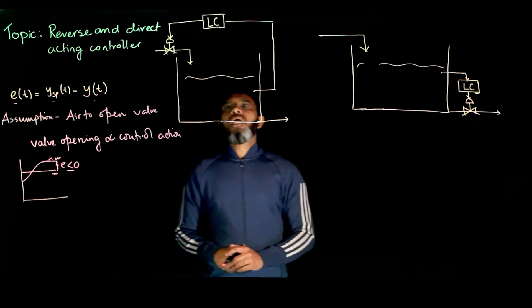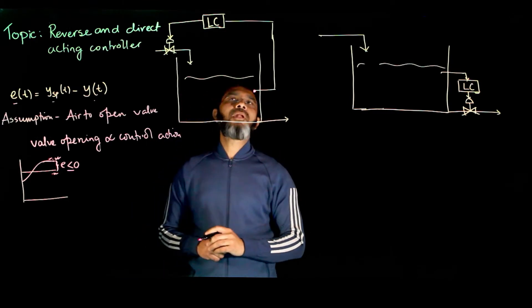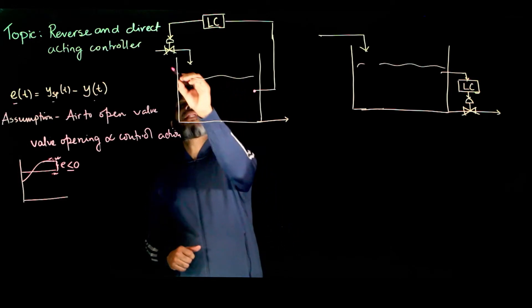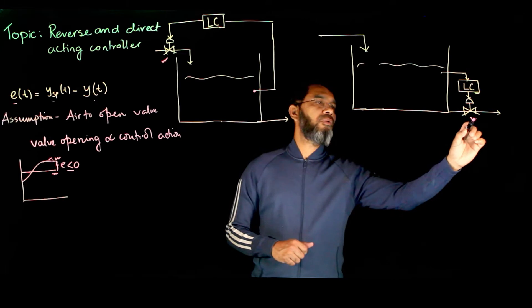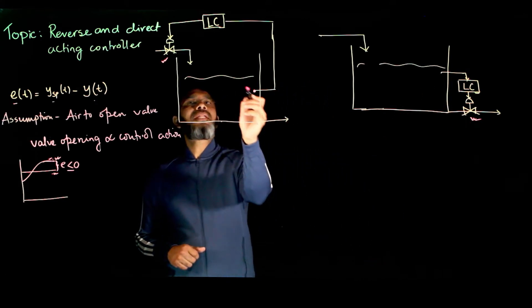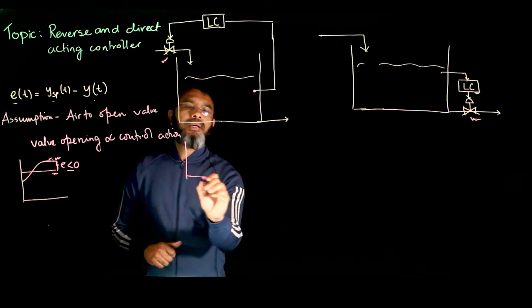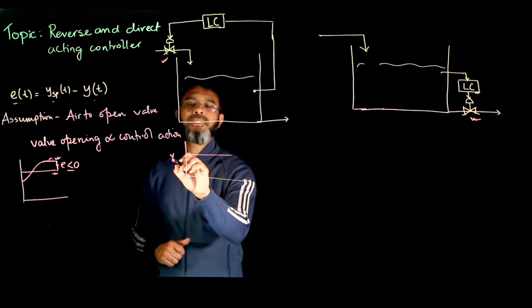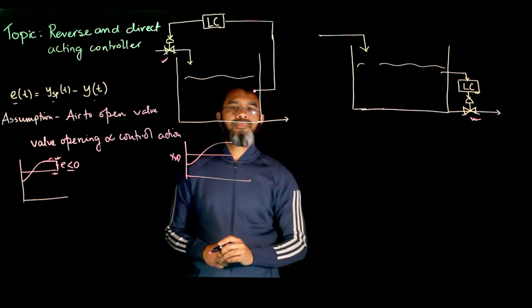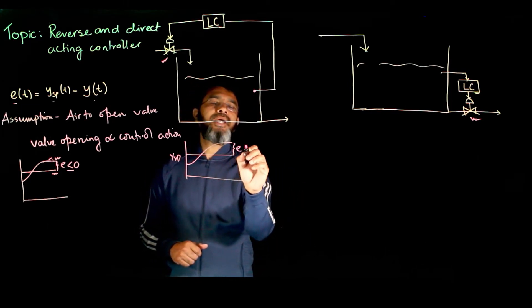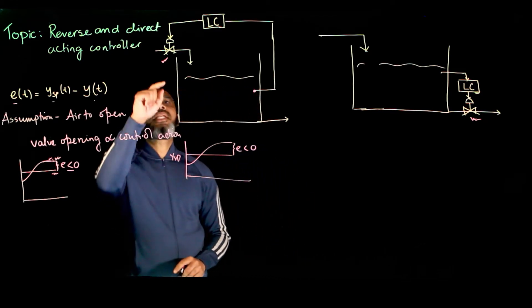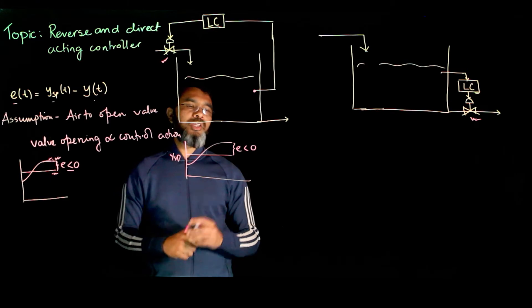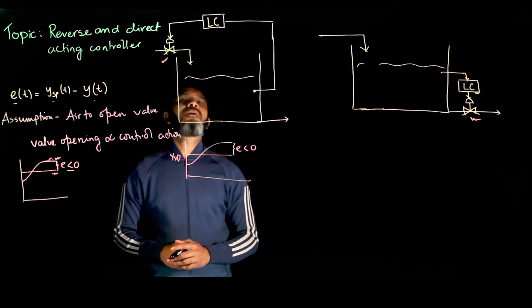Now consider the tank example where you want to maintain the liquid level. You can maintain the level by manipulating either the inlet flow or the outlet flow. When manipulating the inlet flow, suppose the desired value is the set point and the output goes beyond it — the error is negative. We assume the valves are air-to-open valves, meaning to open the valve you need instrument air, and more air pressure means more valve opening.